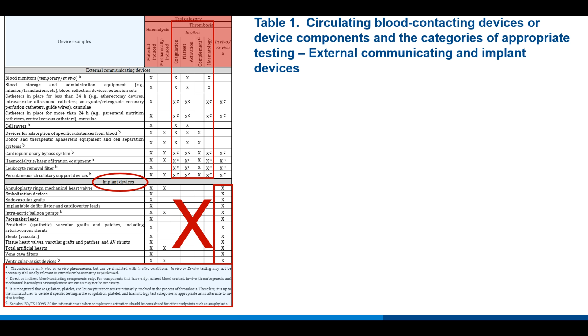that apply there. But it's important to point out that people work very hard at putting in this little bit of footnotes here, and I'm going to expand that so you can see it a little better. But importantly, it points out that thrombosis is an in vivo or ex vivo phenomena, but it can be simulated with in vitro conditions. So in vivo or ex vivo testing might not be necessary if clinical relevant in vitro thrombosis testing is performed. So for those of you out there who are involved in this, it's important to point out that there is an in vitro opportunity here, and I'll give some examples of that at the end of this talk if there's time.